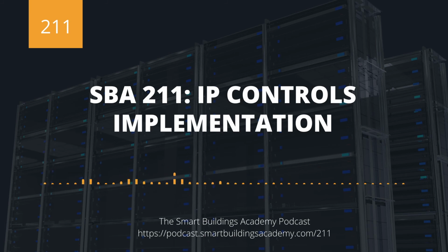But implementation scenario 2: 30-story office building, air handling units, VAVs, chillers, boilers, etc., the whole kit and caboodle. So what I like to do here is put some supervisory device in. And the reason why is in this scenario, I like to have a central supervisory device that acts as my single point of reference for graphics. In theory, you could have all these individual IP controllers and have graphics in each one and have your trends and schedules and alarms in each one.